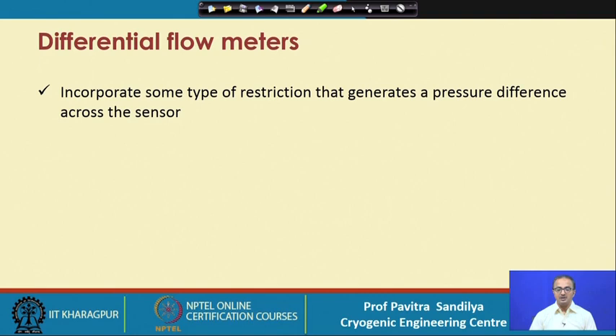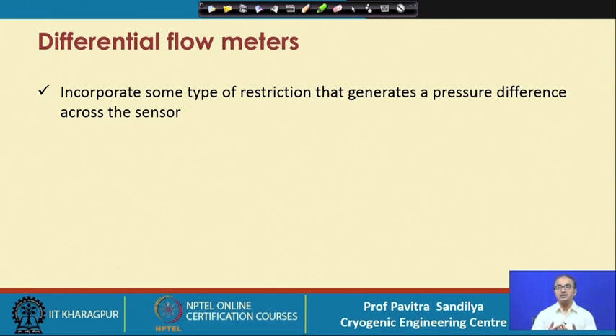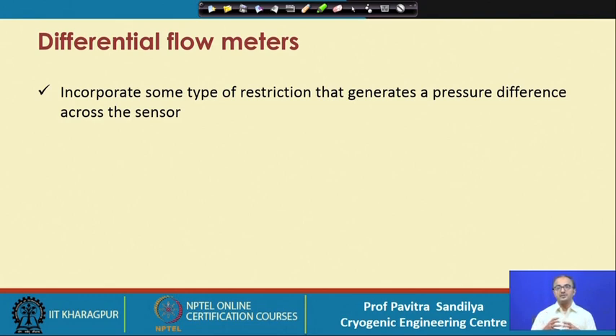Coming to the differential flow meter, let us see how it works. Generally, any fluid flowing in an open or closed channel will experience drag, which creates a pressure drop. Drag is a resistance to the flow of a fluid. This drag may come from skin friction — the friction between the surface and the fluid due to viscosity — or it may be due to form drag, which occurs whenever there is a tortuous, non-straight-line path causing a change in the direction of fluid flow. Because of these drags, there will be a pressure drop along the flow path.